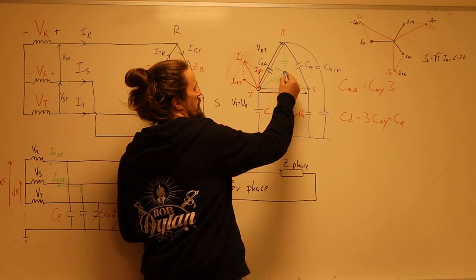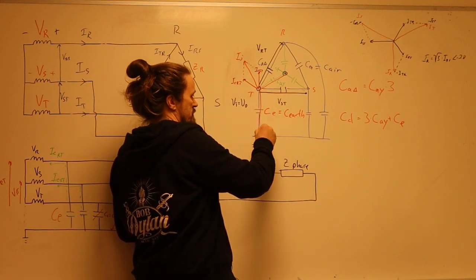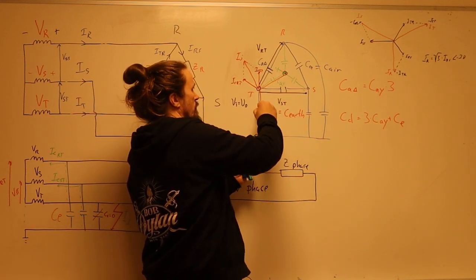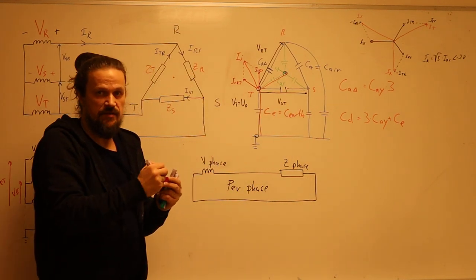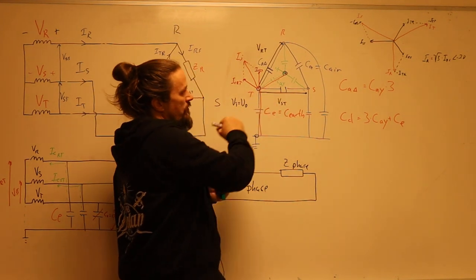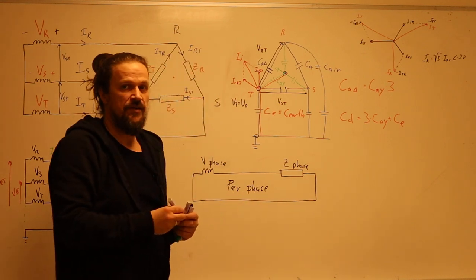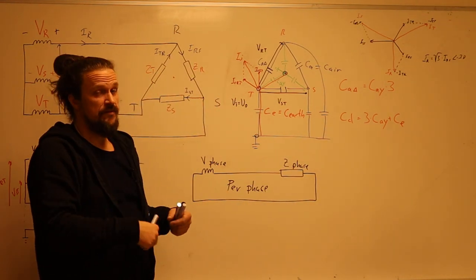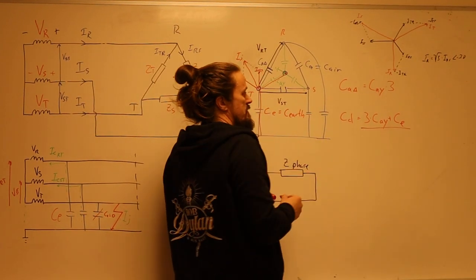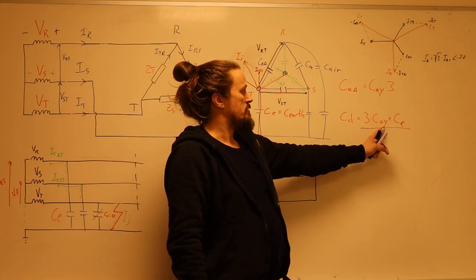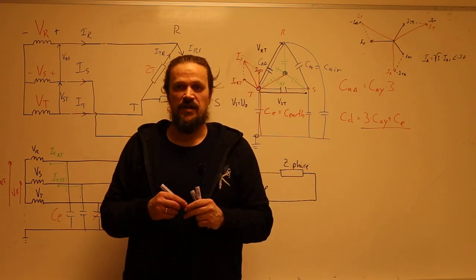The whole concept here is that I know something about the connection from the star point to the t point, and then I already know the connection to earth, the capacitance to earth. That's basically the thing that I need to compute. Since these two points are at the same potential, it means that they are in parallel. When we have capacitances we can merely sum them together. This cd which in Norwegian is the driftskapasitans, which we are given in a per phase, can be computed by three times c air star connection plus the connection from c to earth.